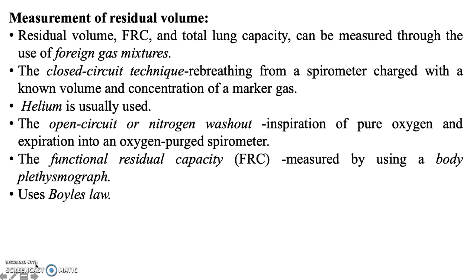Here, the patient breathes air through a tube containing an airflow transducer. So here also the patient will be inhaling the gas through a tube, but you will have a transducer here so that we can monitor the airflow. The tube through which the patient is breathing is usually closed off with the help of a shutter. That is, the patient has to make some extra effort or pressure to inhale the gas, and hence the ratio of change in lung volume to change in mouth pressure is used to determine the gas volume.